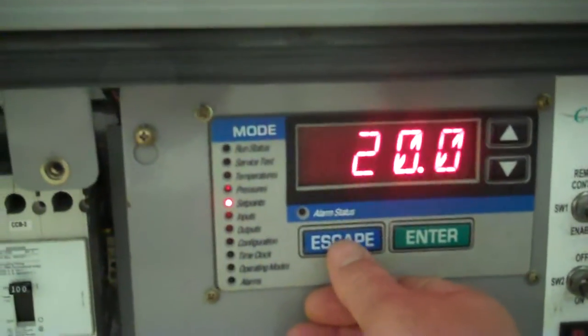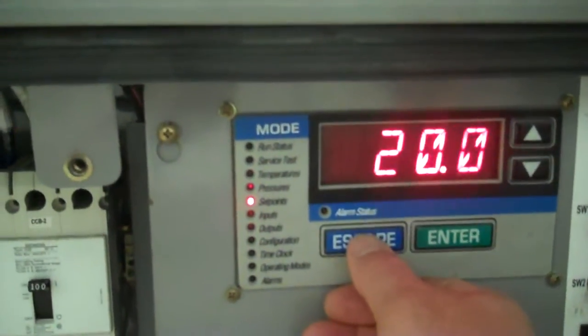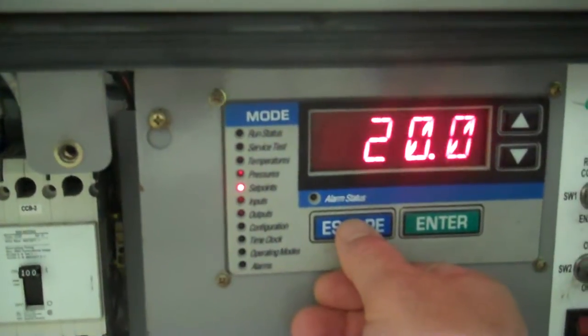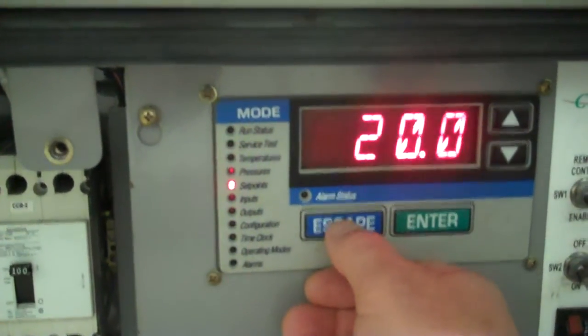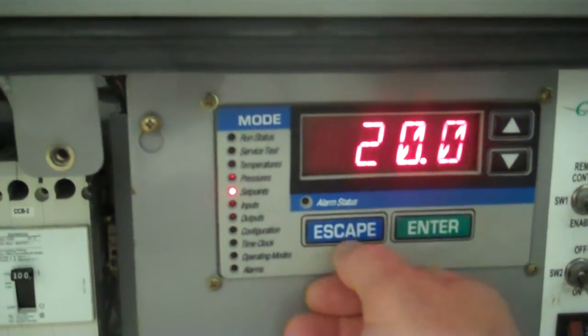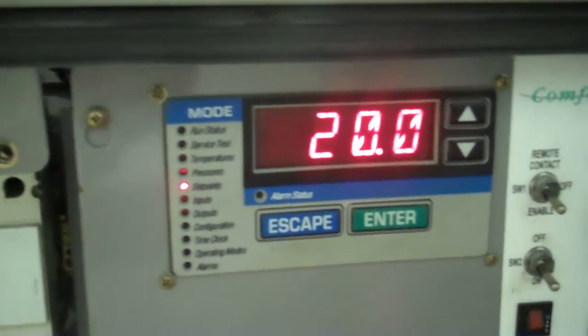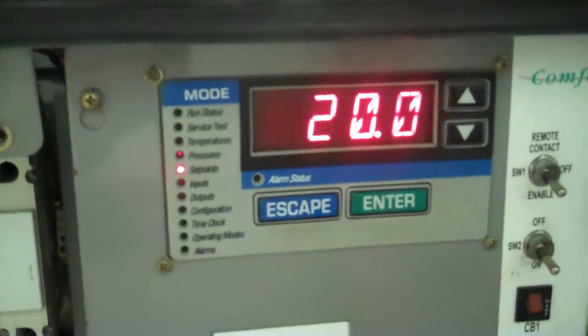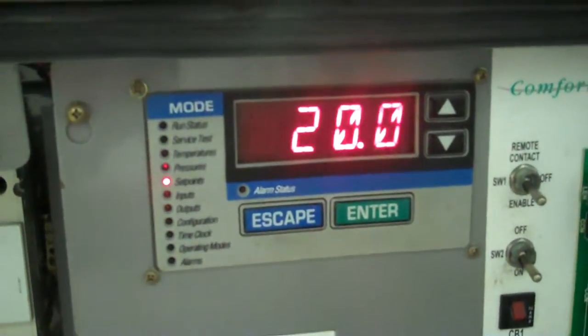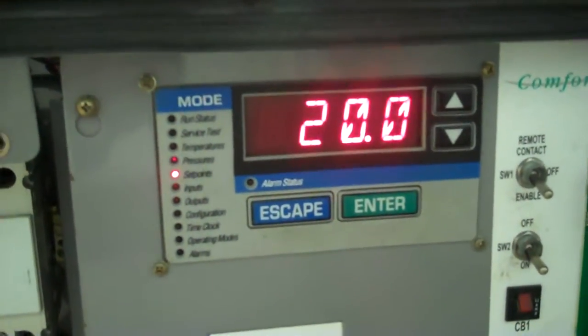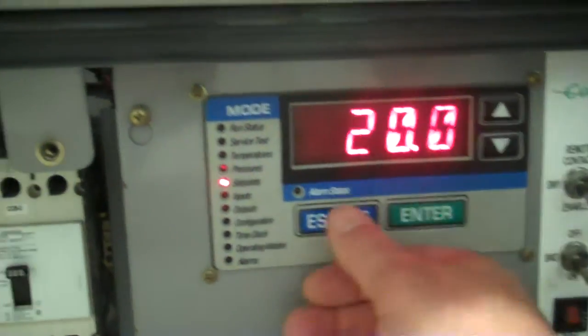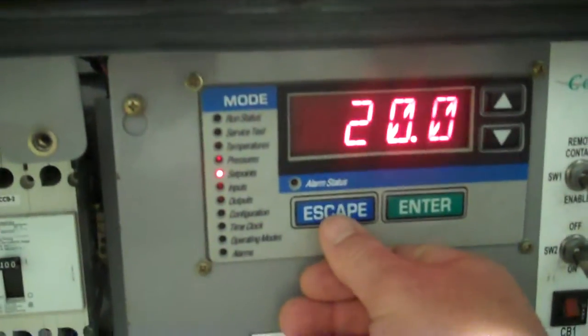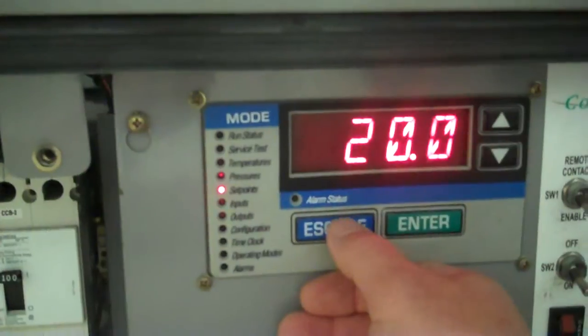I did just press the enable button. There is typically a delay before it turns on and starts chilling. That's for safety upon a fresh start up just to ensure that there's water flowing through the system before the compressors turn on.